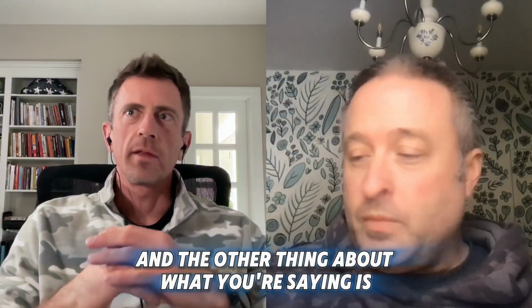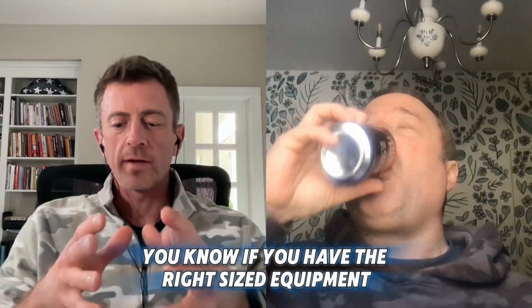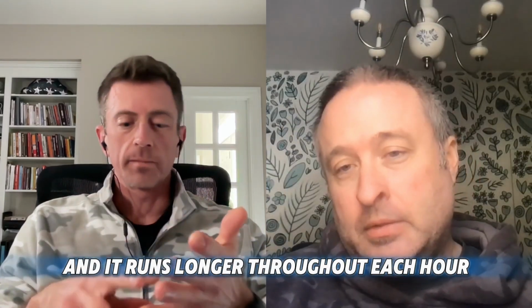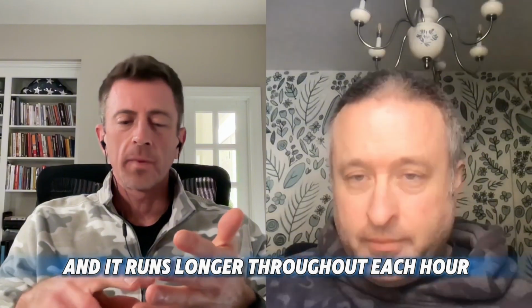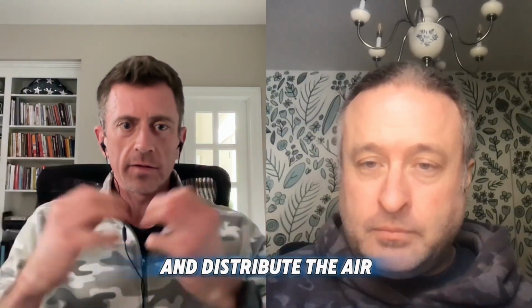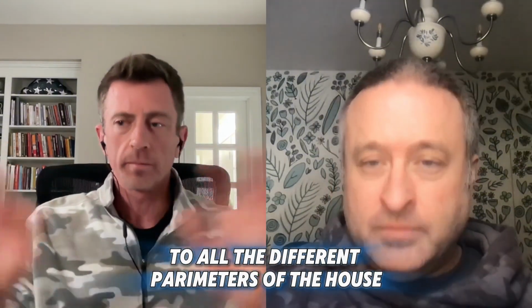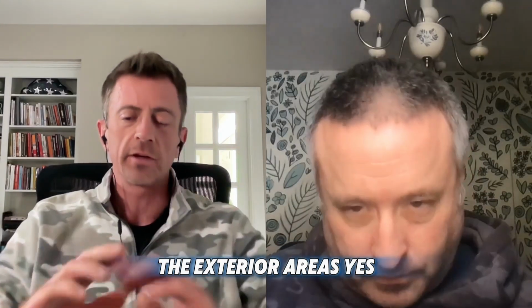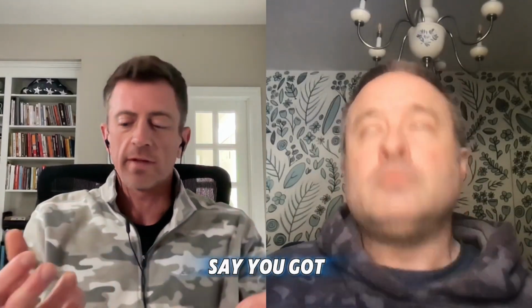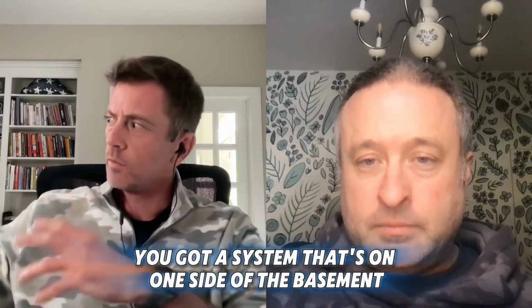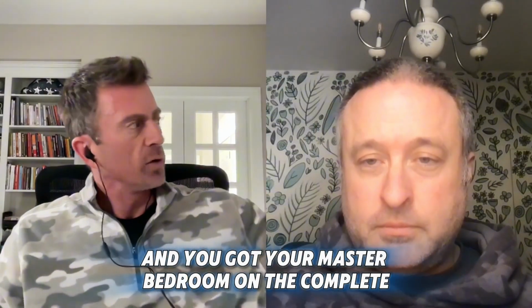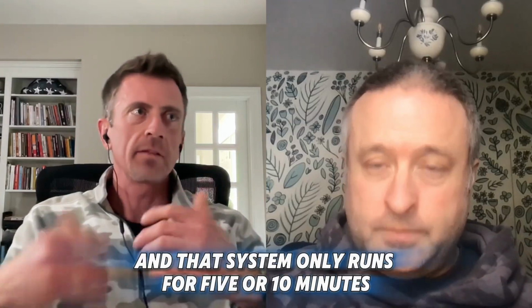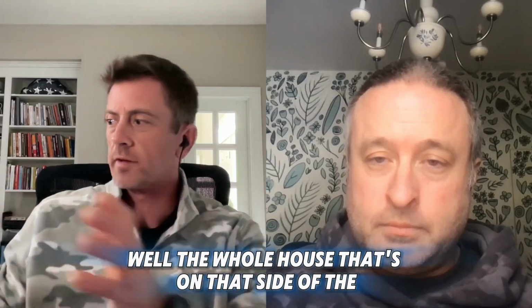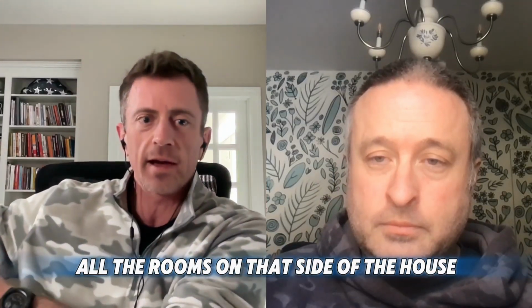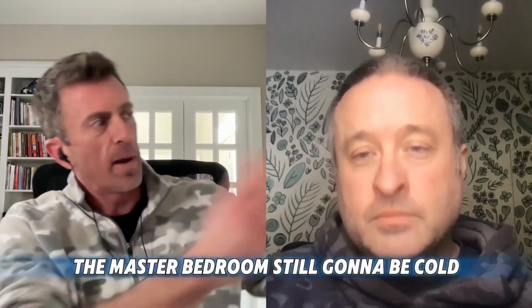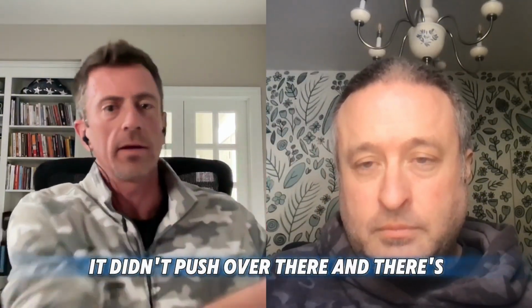Now, the other thing about what you're saying is, if you have the right sized equipment, it runs longer throughout each hour, it's going to push the air throughout the house and distribute the air to all the different perimeters of the house, the exterior areas, more evenly. Because say you've got a system on one side of the basement and your master bedroom on the complete opposite side of the house, and that system only runs for 5 or 10 minutes, well, all the rooms on the side of the house where the furnace is are going to be warm, right? The master bedroom's still going to be cold because the air didn't push over there far enough.